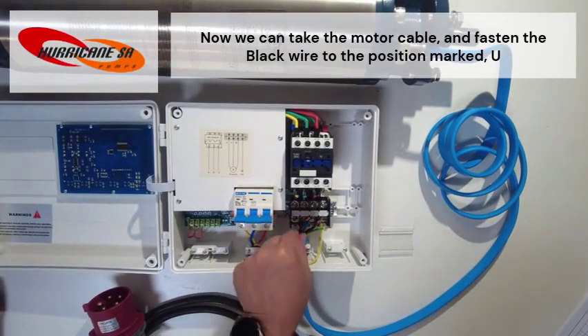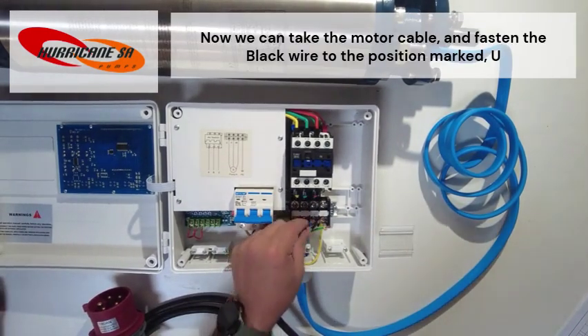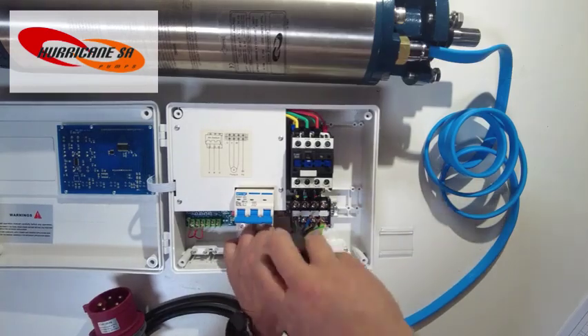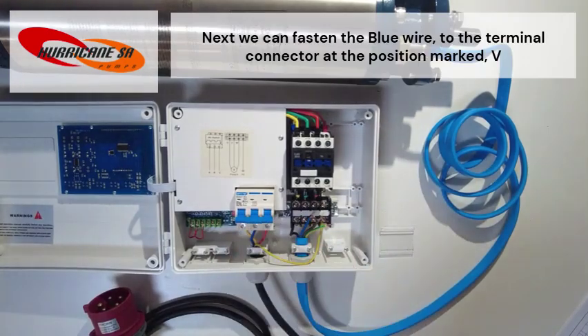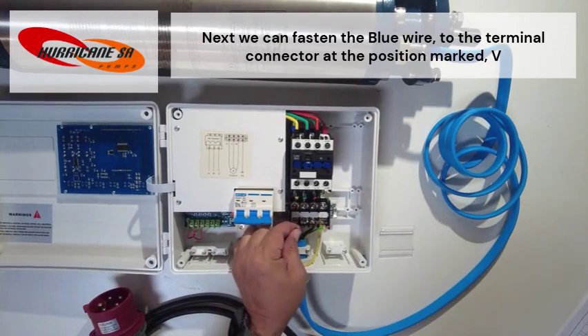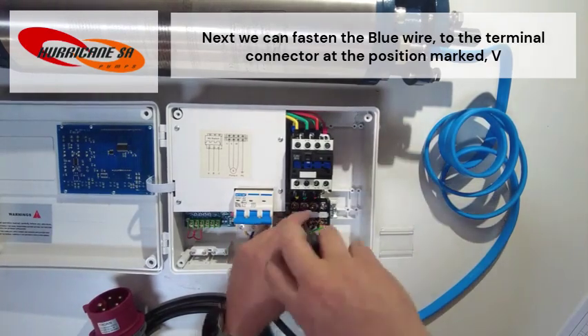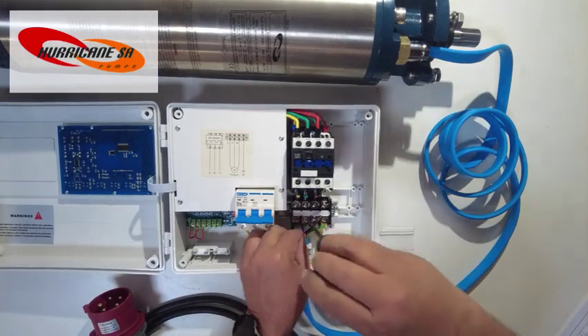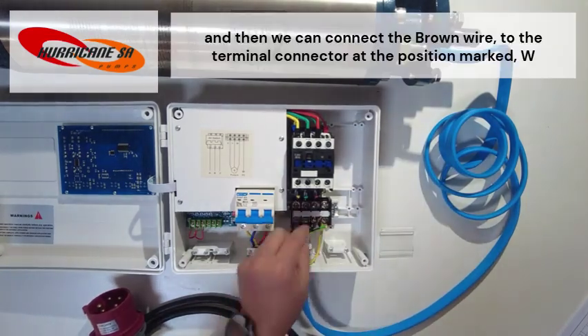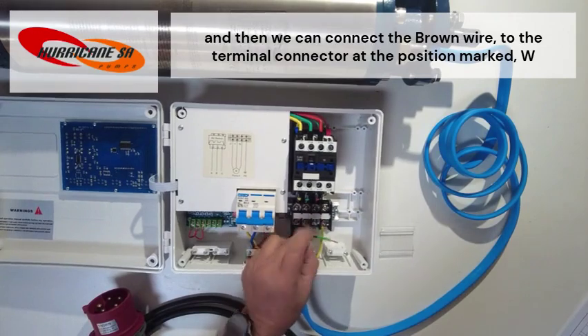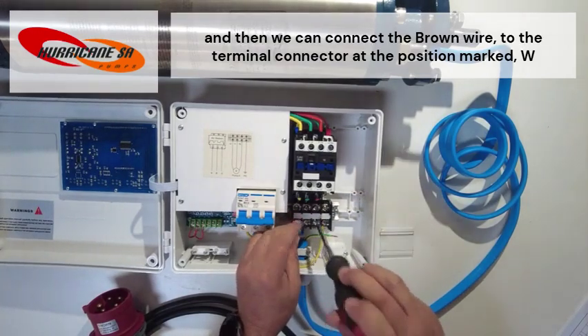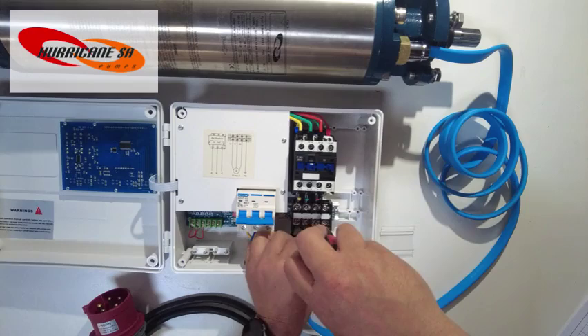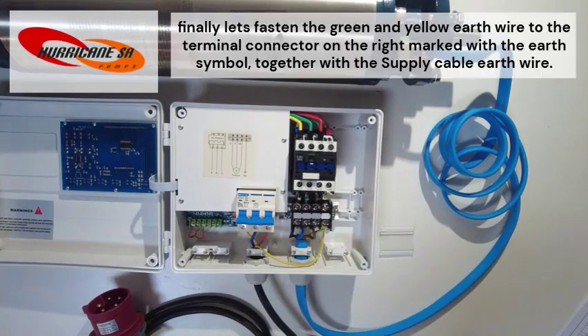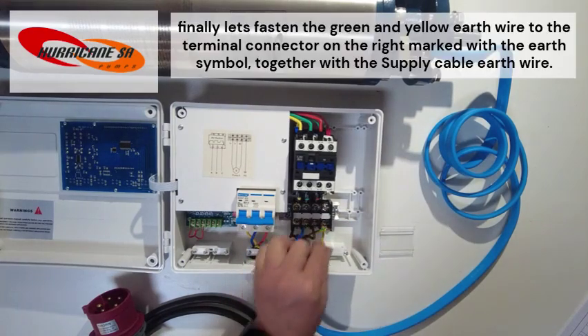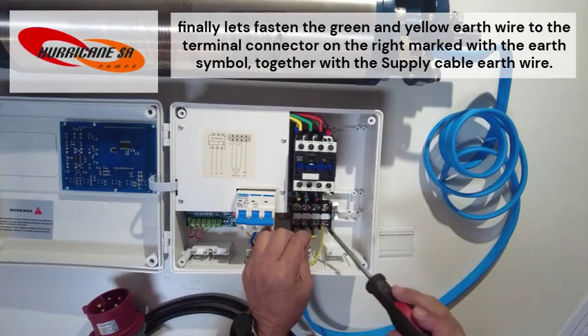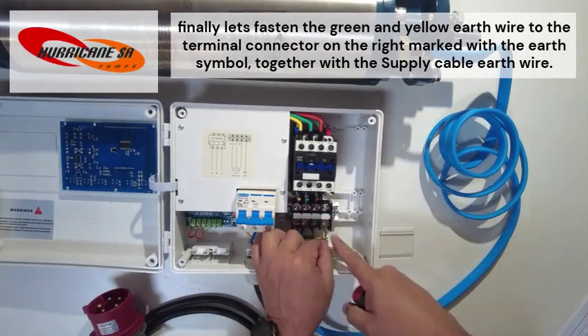Now we can take the motor cable and fasten the black wire to the position marked U. Next, we can fasten the blue wire to the terminal connector at the position marked V. And then we can connect the brown wire to the terminal connector at the position marked W. Finally, let's fasten the green and yellow earth wire to the terminal connector on the right marked with the earth symbol, together with the supply cable earth wire.